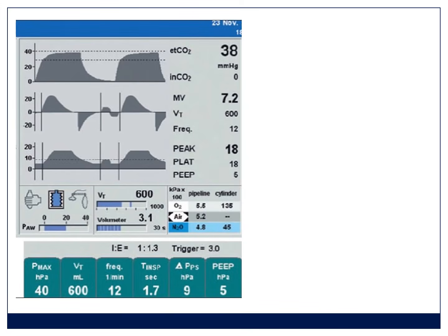And you should practice. Now, this is a slightly more advanced anesthetic machine. And here we're doing SIMV mode plus pressure support. And so there's the pressure support. So this patient's dialed in 600 mils tidal volume at a rate of 12. They've set the maximum pressure at 40.